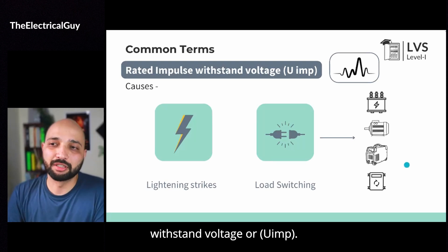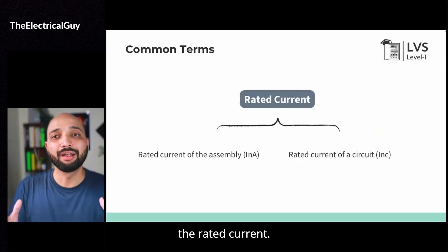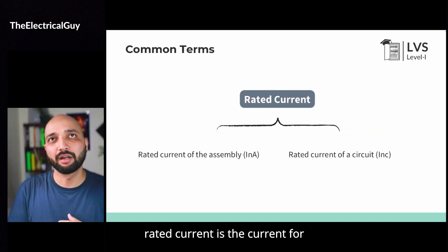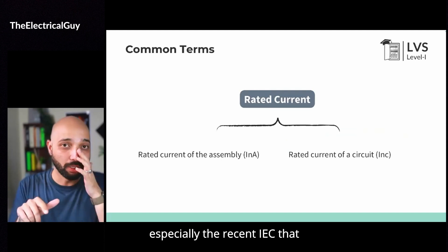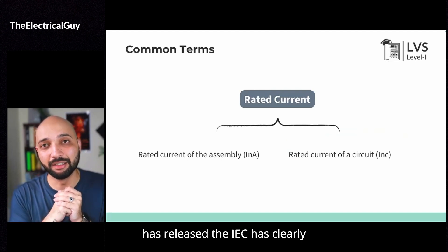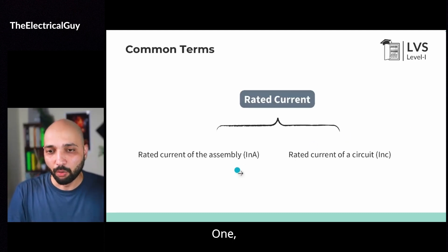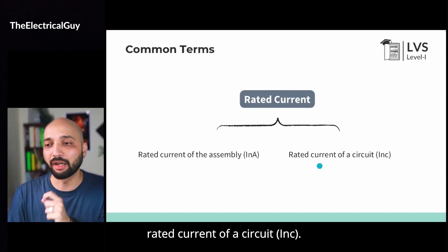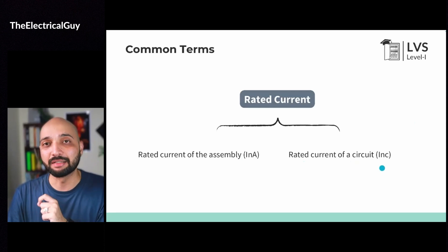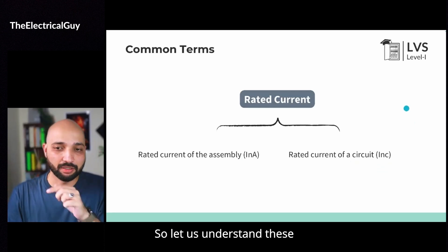So that is rated impulse withstand voltage or UIMP. Moving on, the first parameter to address now is rated current. The IEC has clearly distinguished the rated current into two different parameters: one is the rated current of the assembly (InA), and the second is rated current of a circuit (InC). These are the two bifurcations done by the recent IEC. Let us understand these two terms.